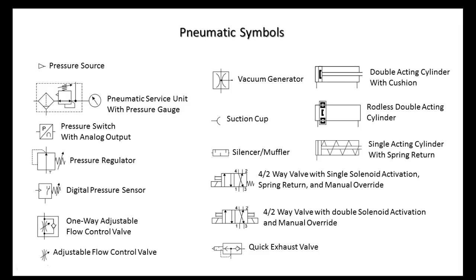That makes sense. Now, the problem with these things is when I push on this side, we push against more area. When I push it on this side, we have to subtract the rod. So these guys can generate more force when you extend them than when you retract them, because force is equal to area times pressure. A rodless cylinder has no rod, so it'll generate both forces going left or right.